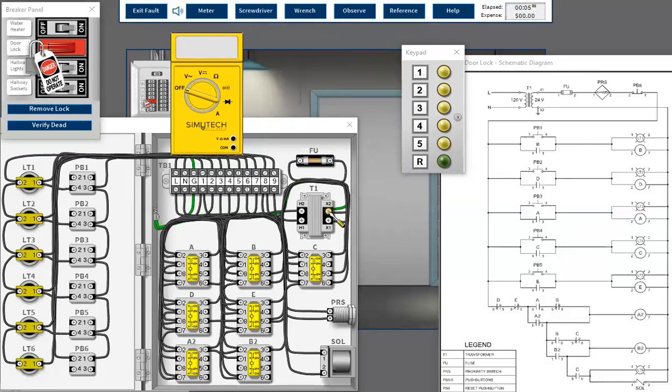I would check at my transformer real quick and just make sure those are good. It could be a coil that's high resistance or low resistance, sorry. Everything ought to check about 71 ohms at the low end. Nope, so we're not having a problem there. It's only when... or a neutral. I could have a loose neutral or something. Bad connection there.